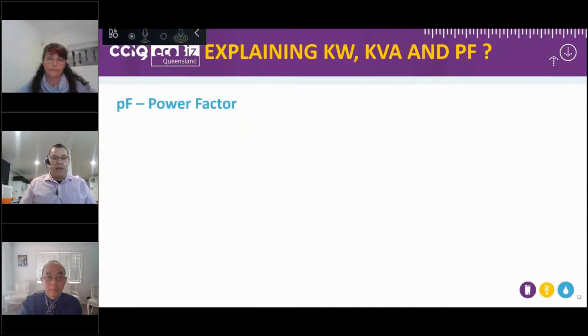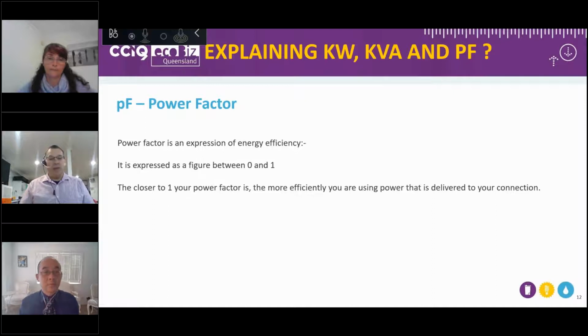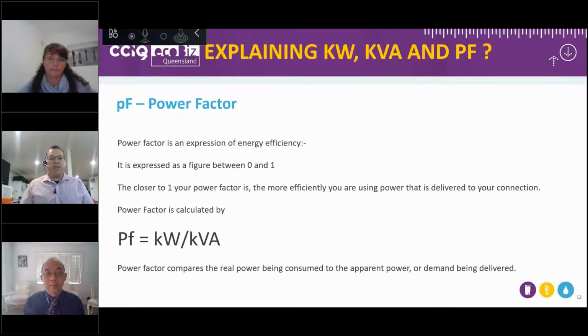Thank you. And power factor. Power factor is an expression of energy efficiency. It is expressed as a figure between 0 and 1, and the closer to 1 that your power factor is, the more efficiently you are using power that is delivered to your connection. Power factor is calculated by the simple formula of kilowatts divided by your kVA, your kilovolt amps. Power factor compares the real power being consumed to the apparent power, or the demand, being delivered. So again, it's an element of efficiency.